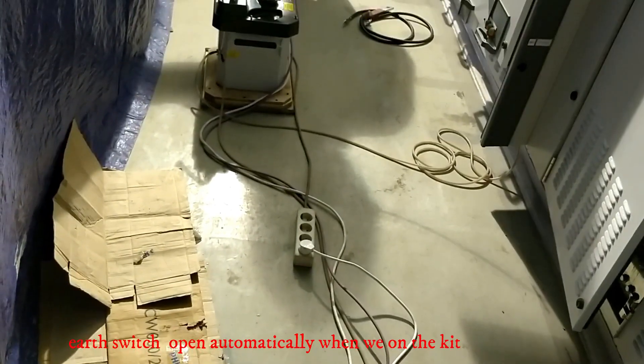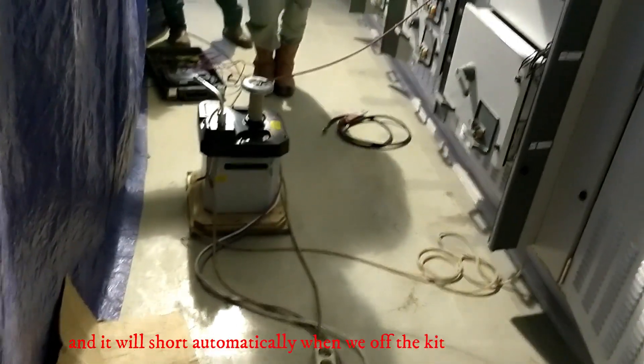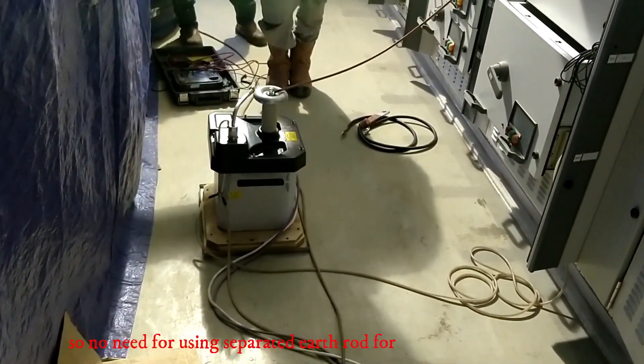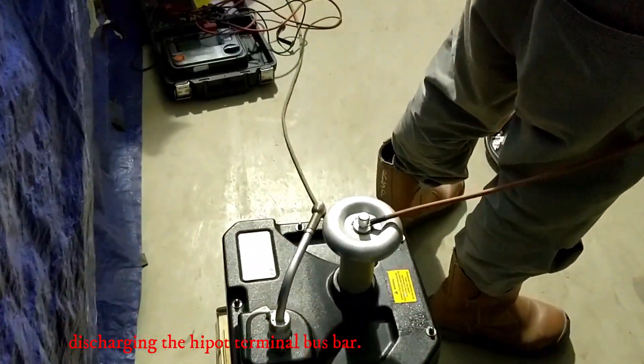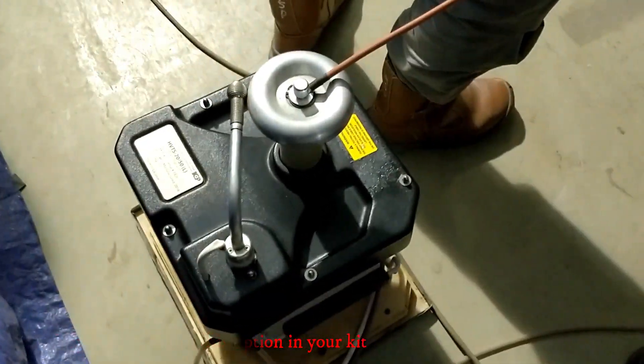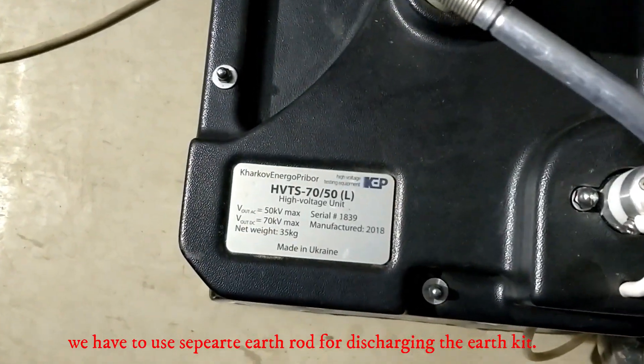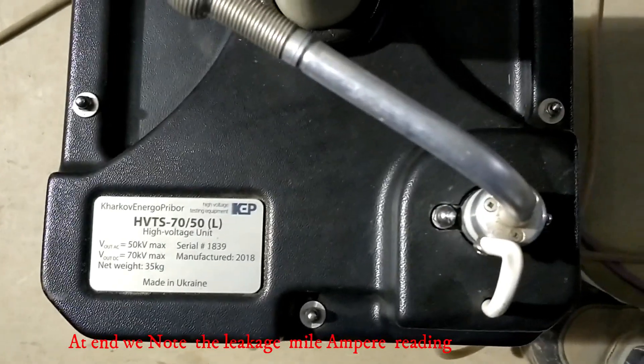The earth switch opens automatically when we turn on the kit, and it will short automatically when we turn off the kit. So there is no need for a separate earth rod for discharging the hypot terminal for bus bar. But if you don't have this option in your kit, you have to use a separate earth rod for discharging the bus bar. At the end, we read the leakage mA from the kit.